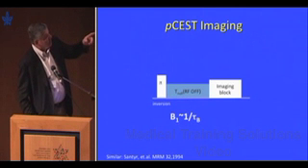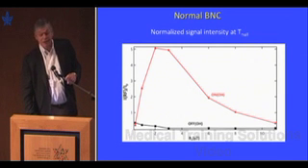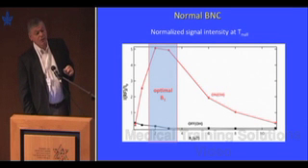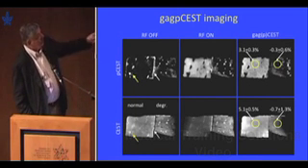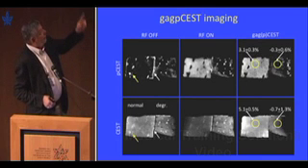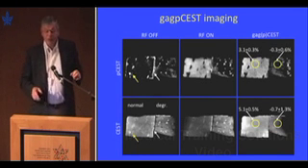It really suppresses it. So then you use an imaging sequence, a fast imaging sequence, and in the gray part, you either irradiate on frequency or off frequency, and you take an image, and you can actually get quite a nice signal intensity difference if you do this right here at the optimal B1 field. And that depends on the exchange rate of the protons. So if you do this, you can actually make very nice images of, now this we've only done in ex vivo cartilage, and here's the positive CEST, and here's the negative CEST, and you can see you get slightly lower CEST values, but the background's completely suppressed, and that has a big advantage in vivo.